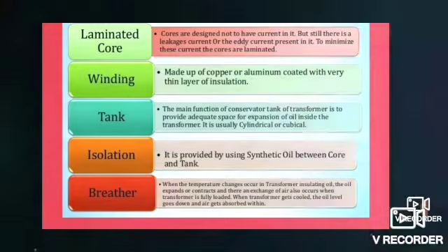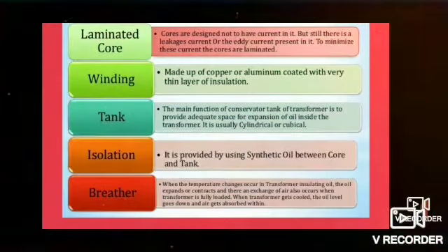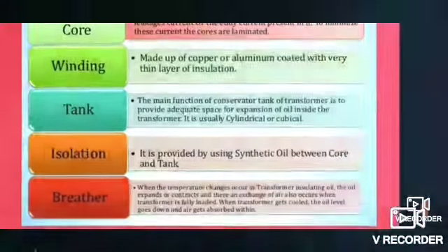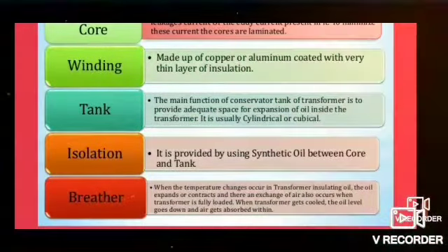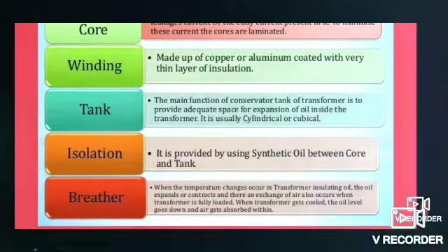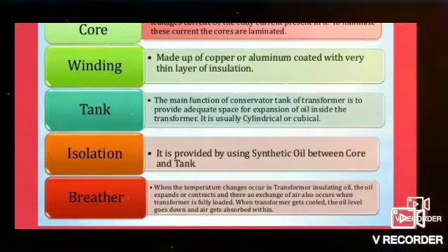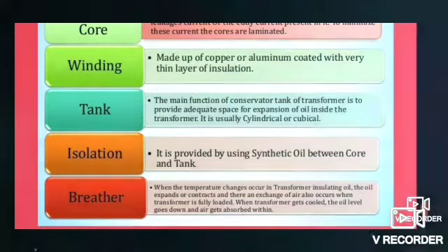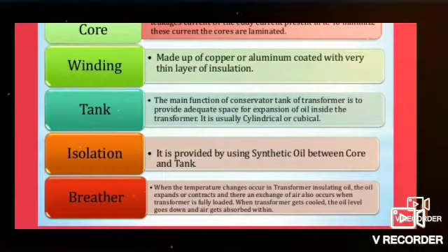Then there will be a breather. When temperature changes occur in the transformer insulating oil, the oil expands or contracts and an exchange of air also occurs when the transformer is fully loaded. When the transformer gets cooled, the oil level goes down and air gets absorbed within. That is the function of the breather.